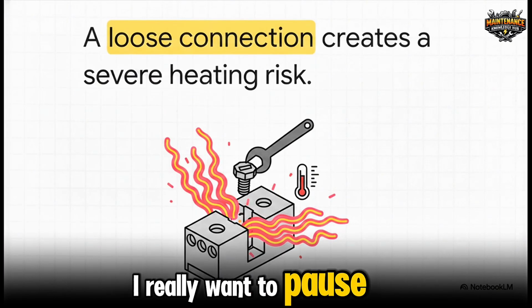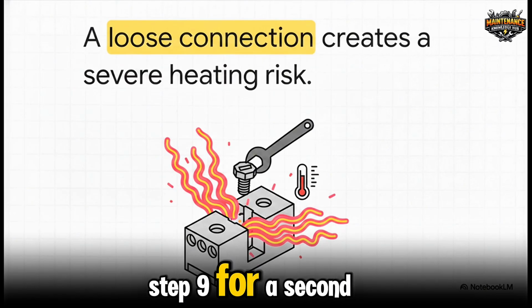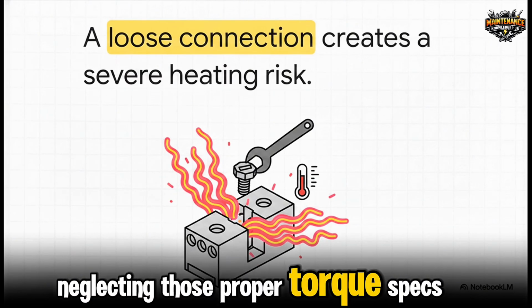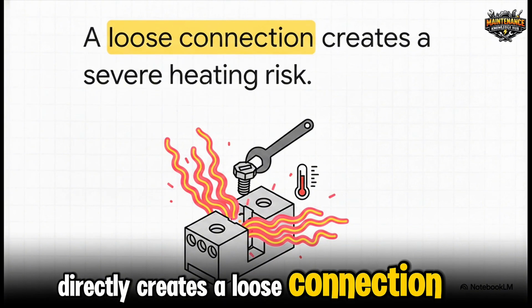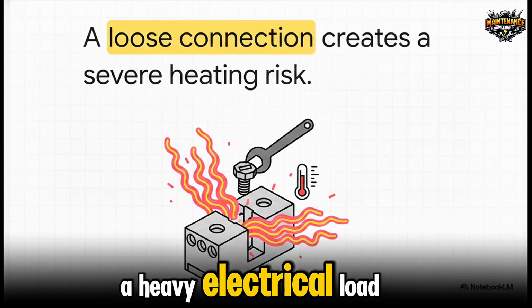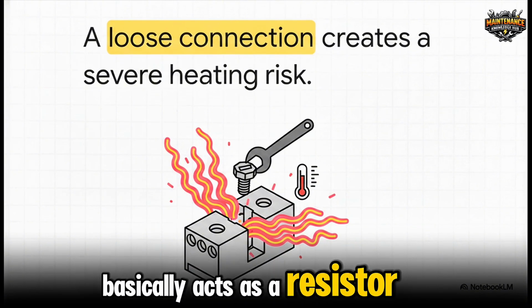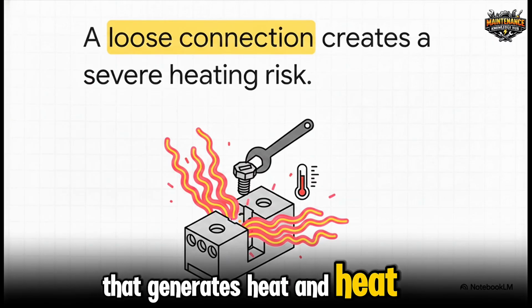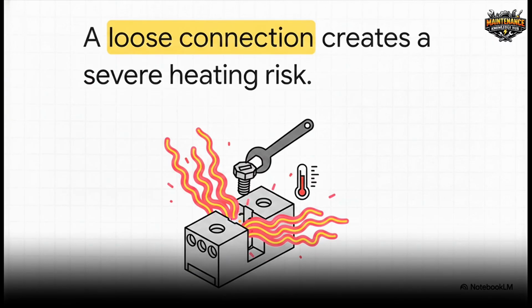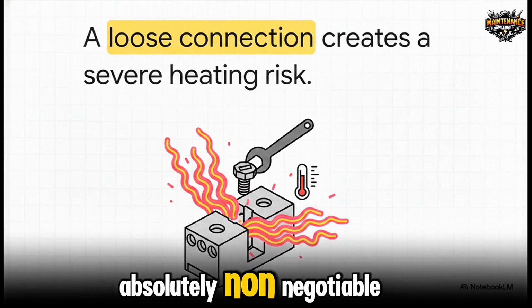I really want to pause and emphasize step 9 for a second. Neglecting those proper torque specs directly creates a loose connection, and a loose connection under a heavy electrical load basically acts as a resistor. That generates heat, and heat means a massive fire risk. Precision on this step is absolutely non-negotiable.